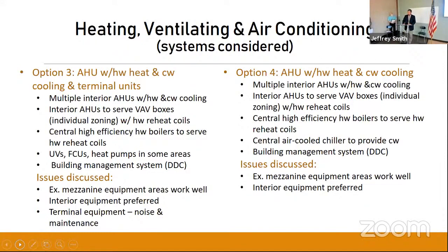Option 4, we looked at air handling units with hot water and chilled water coils, VAV boxes to meet all of the zoning requirements, and the ductwork. A central high efficiency boiler plant. The way we would size the boilers, we would have some spare redundancy capacity for you. That way, if you lost one, you would have multiple smaller boilers, and you could take one out of service and still maintain the operation of the facility. A central air-cooled chiller at grade level, so that it would be outside the building, easy to maintain, replace compressors. We would also have multiple units so that you again had some redundancy if you had to take one offline.